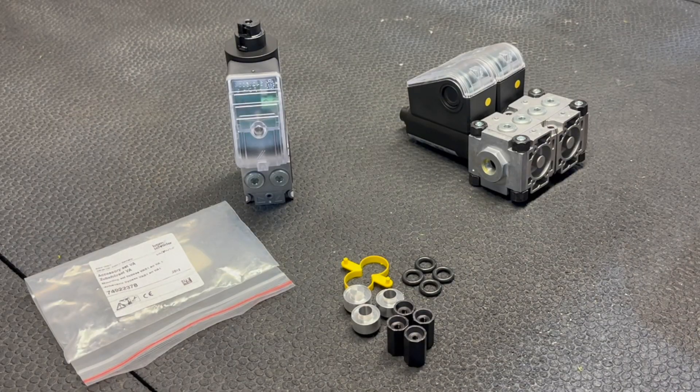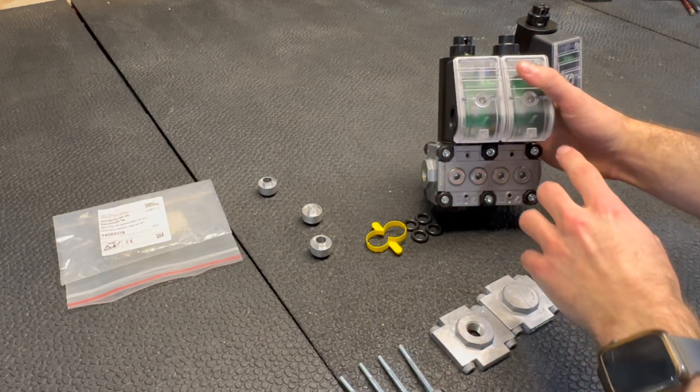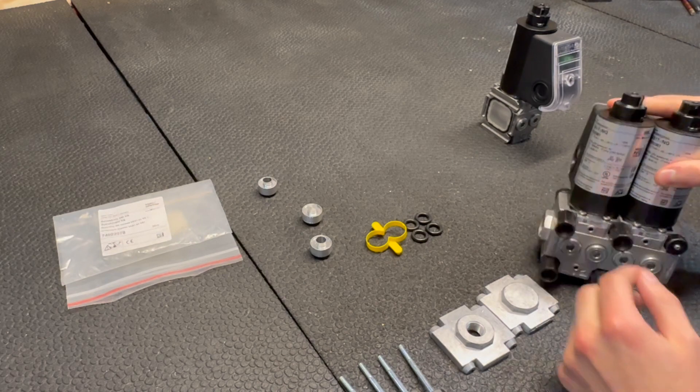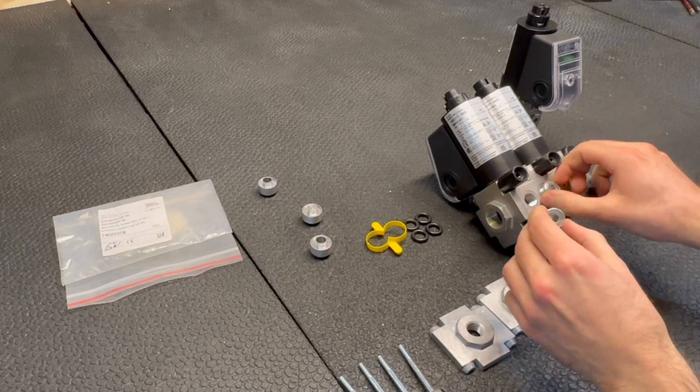Kromschröder also offers a bypass kit to make use of a third valve. For example, if you need a pilot or want high fire/low fire ability, you can do that just by adding this kit and a third valve. To put together the bypass kit, find your second valve and remove the nuts on the bottom and replace them with the extended nuts that come in the kit. After that, remove these plugs — you'll need an Allen wrench.